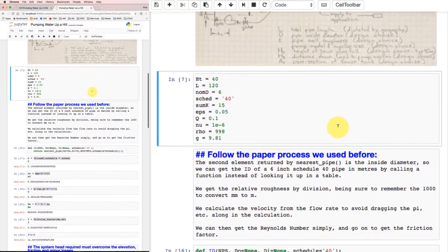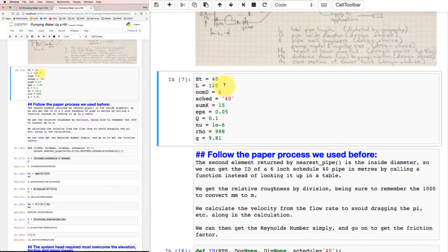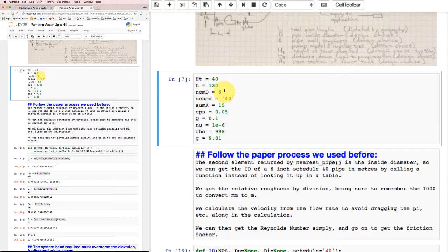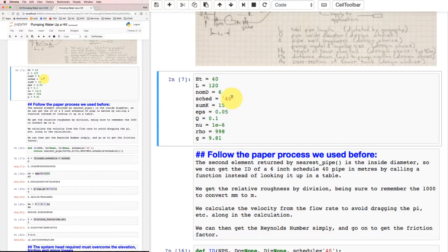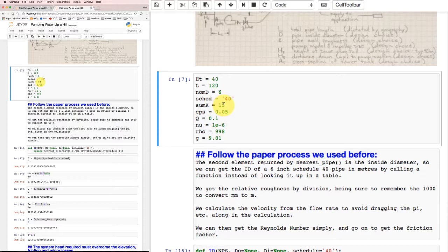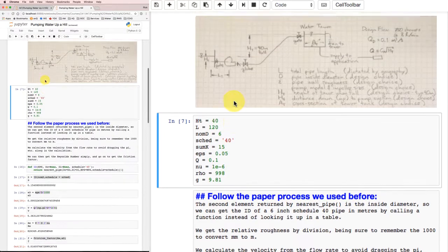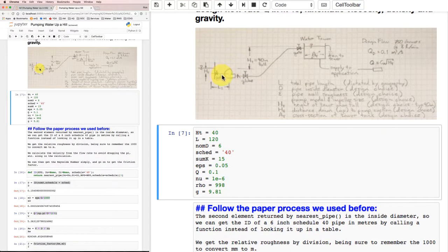In this cell, I'm setting the height of the tank at 40 meters, the length of the piping 120 meters. We're only dealing with a small zone right down by the lake where we're going to run our own water system. I've set the piping to be 6 inches nominal diameter, which I picked when we first tried this example. And I'm choosing Schedule 40 pipe. Pipe comes in different schedules or weights. Schedule 40 is fairly typical for low pressure applications in carbon steel.